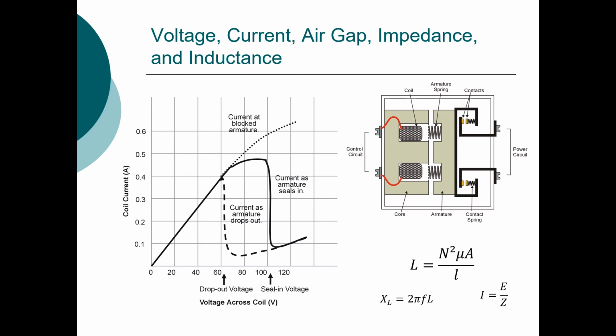If we are to block the armature, which would not allow it to close at all, what we would find is the current would continue to rise to the point where the coil is going to burn out. We always must be aware that a blocked armature will destroy the coil because of excessive heat happening because the current just keeps rising.